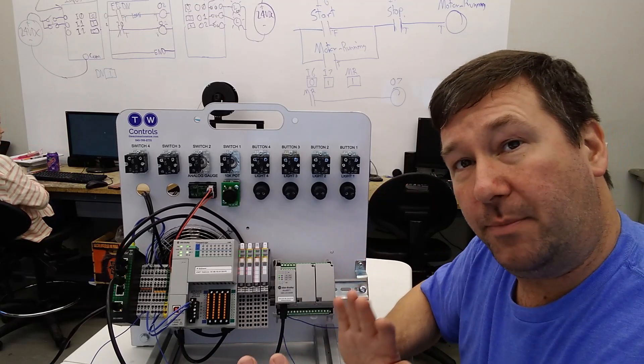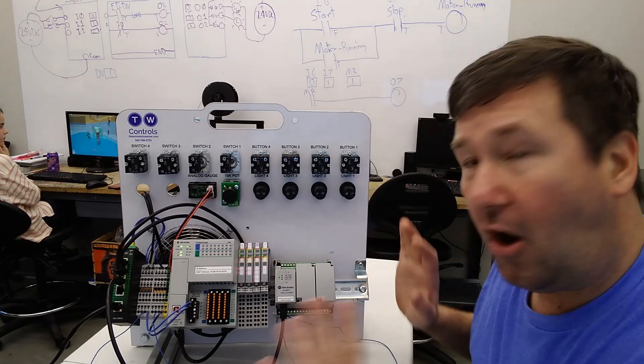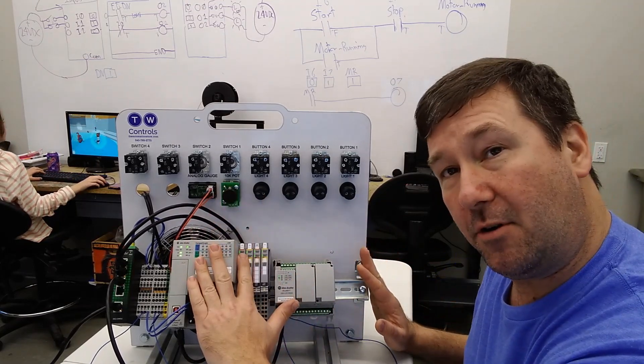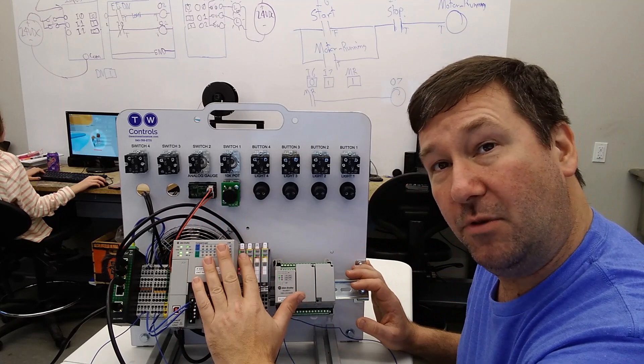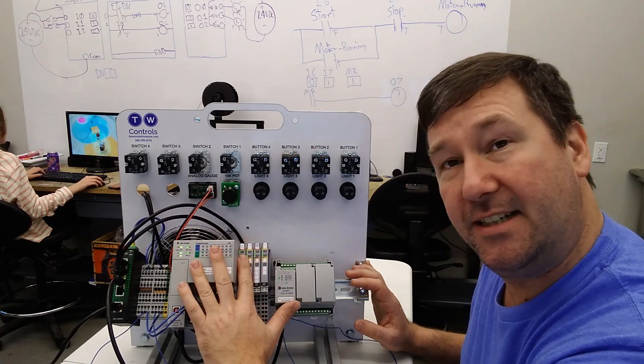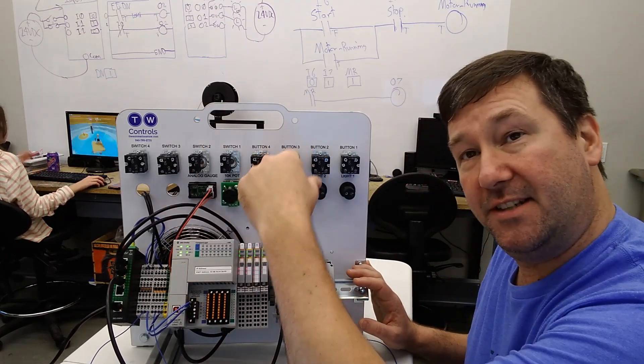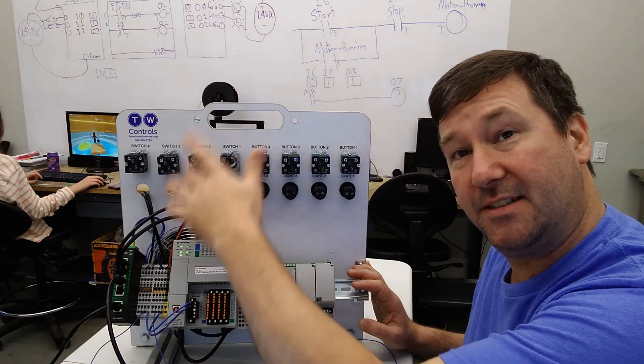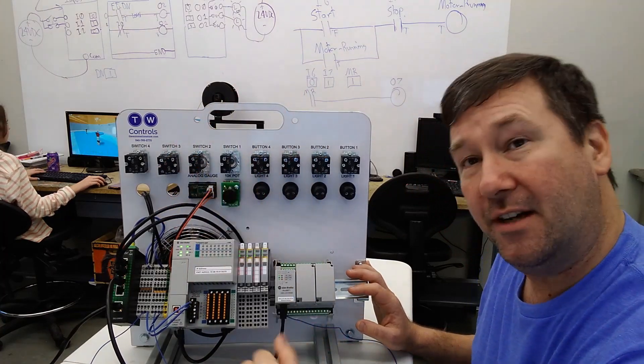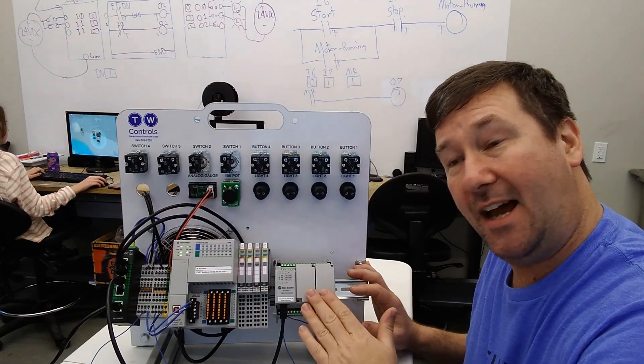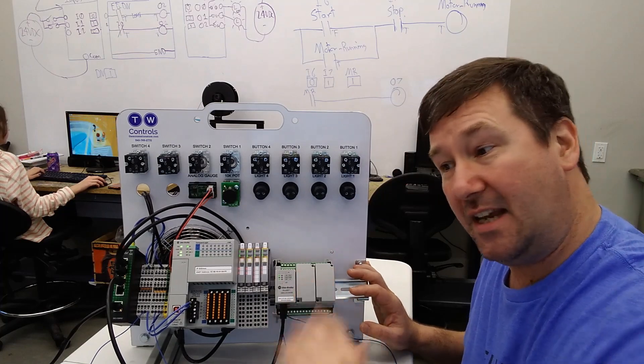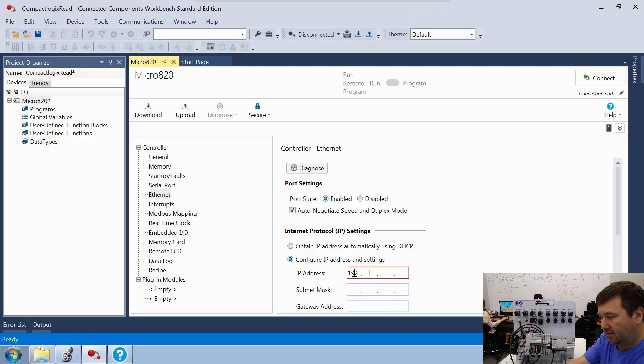This is a unique situation because on all of our trainers, the default IP address of our PLC is 192.168.1.10, and then 11 is the HMI, 12 is the drive on the other side of the trainer. Since we've added this on the side, we're going to need to make it 13. So let's make this 192.168.1.13 with a subnet of 255.255.255.0.